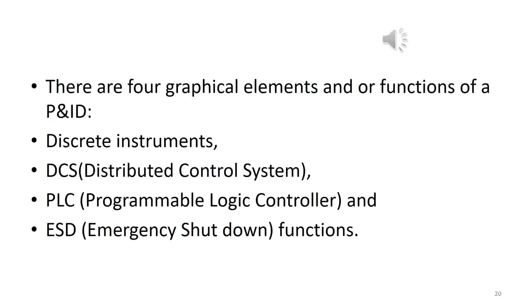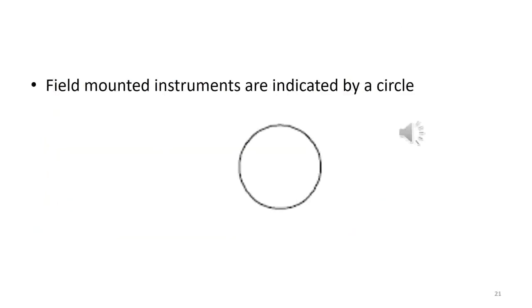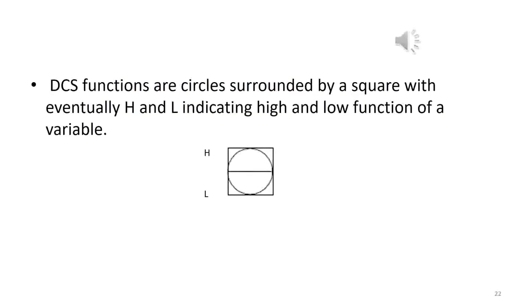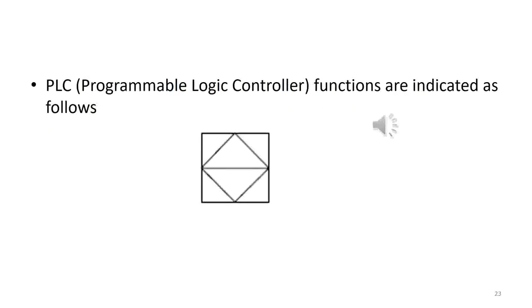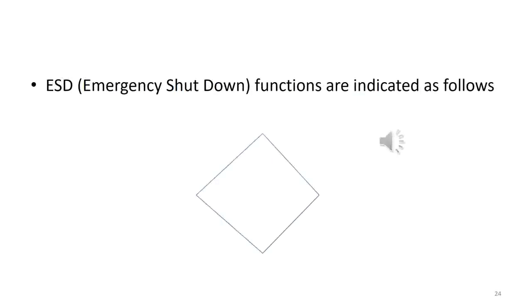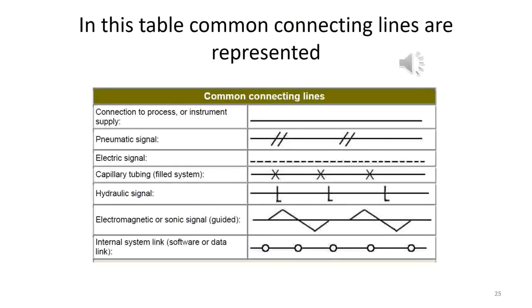There are 4 graphical elements and or functions of a P&ID: discrete instruments, DCS distributed control system functions, PLC programmable logic controller functions, and ESD emergency shutdown functions. Field mounted instruments are indicated by a circle. DCS functions are circles surrounded by a square with eventually H and L indicating high and low function of a variable. PLC programmable logic controller functions are indicated as follows. ESD emergency shutdown functions are indicated as follows. In this table, common connecting lines are represented.